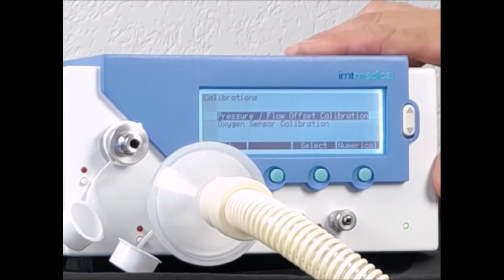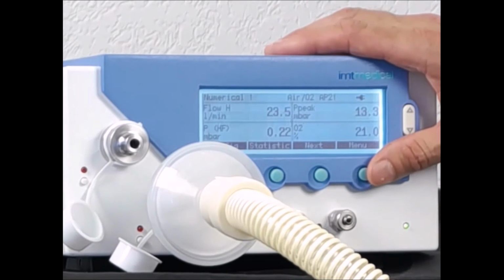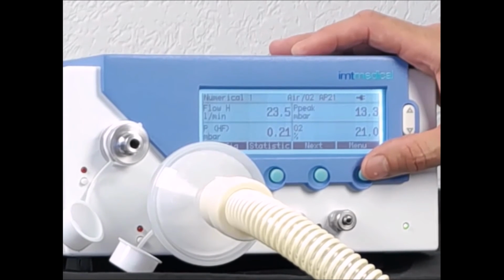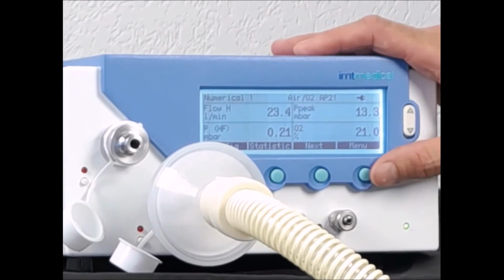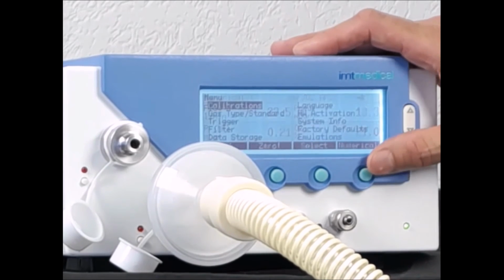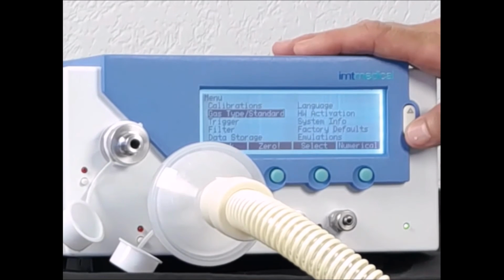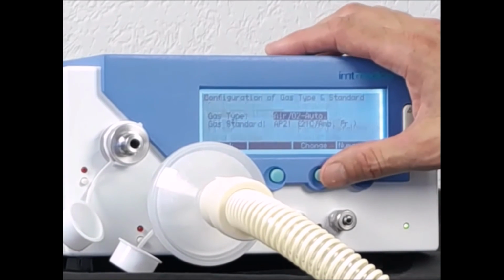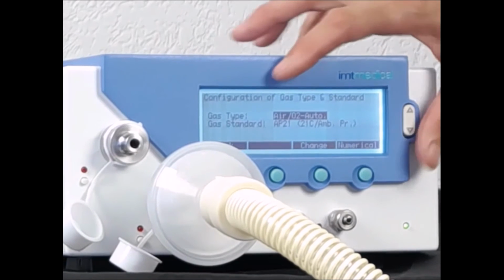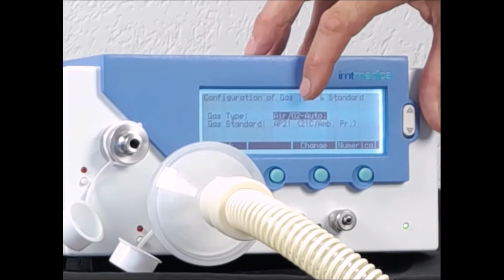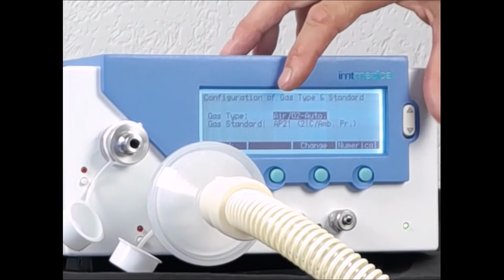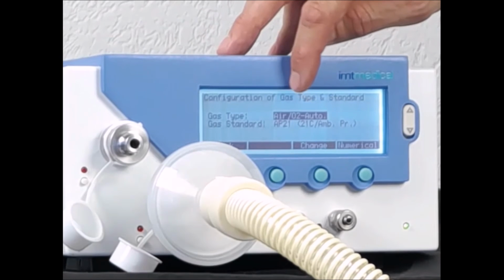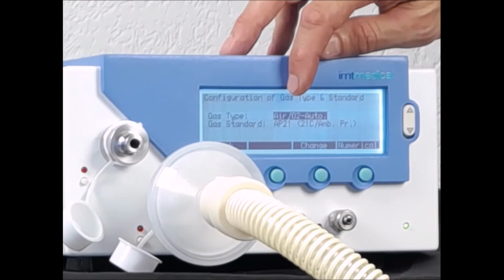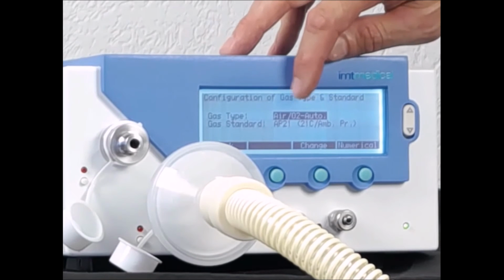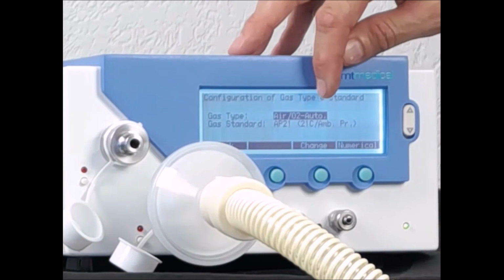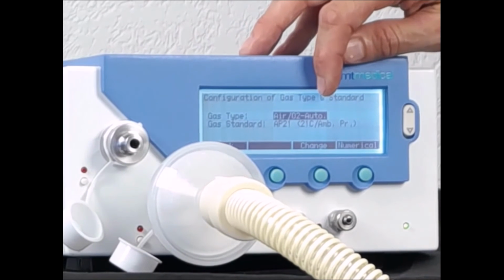As a next step, and we should always do that, we should double check if the gas type, the gas standard, and the trigger settings match up with what I'm doing. I go to the menu, I go to gas type and gas standard, I select it, and I can see now that my gas type is air and oxygen automatic, which means the measurement of the oxygen cell is automatically used to detect what kind of air-oxygen mix is being measured here. So that's correct. That's a typical setting for ventilator and anesthesia machines.